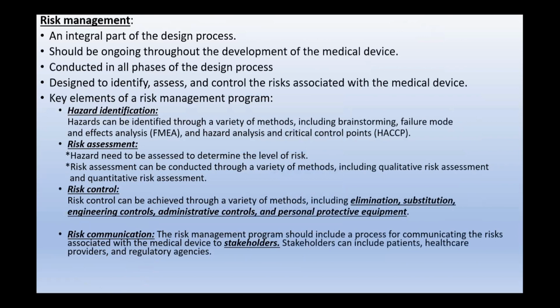The risk management associated with medical devices has to be followed by the manufacturer in the following way. Risk management is an integral part of the design process. It should be ongoing throughout the development of the medical device, conducted in all phases of the design process from start to end, designed to identify, assess, and control the risks associated with the medical device. The key elements of the risk management program are hazard identification, risk assessment, risk control, and risk communication. The risks identified have to be communicated so that we can control them or at least implement control strategies to reduce the seriousness of those risks.